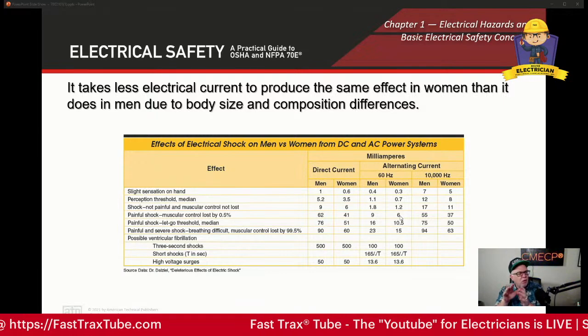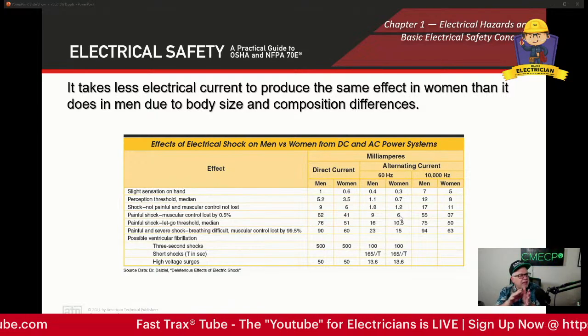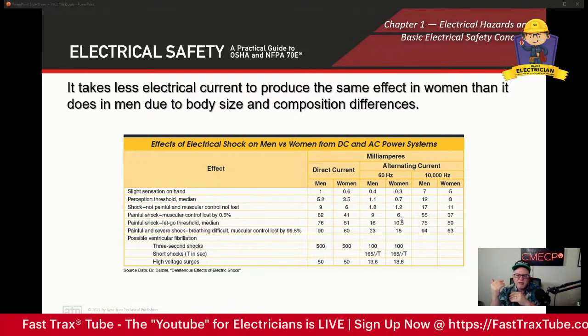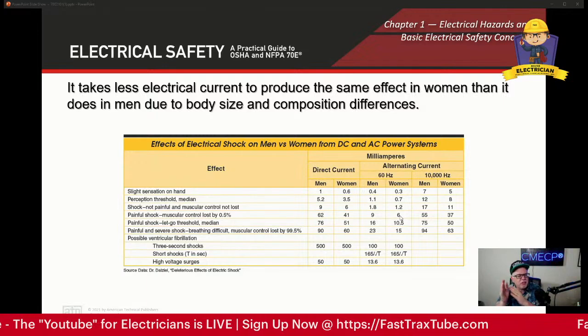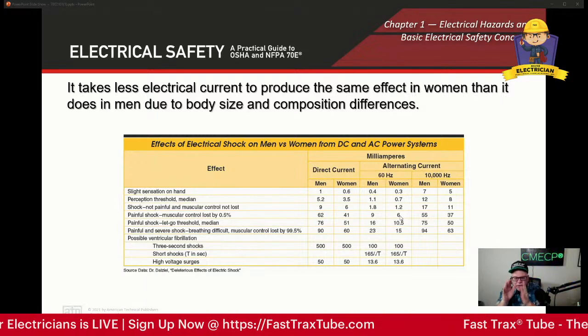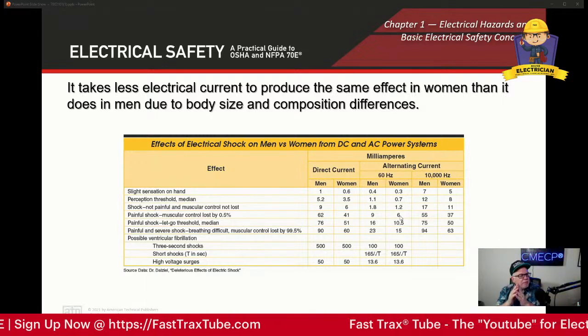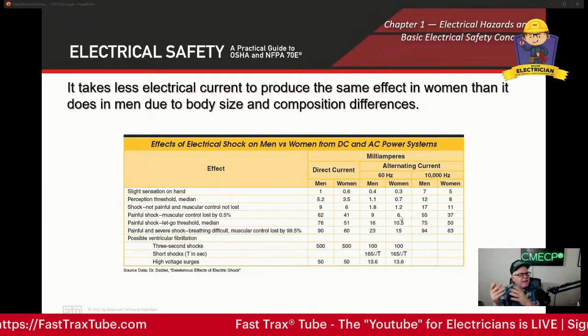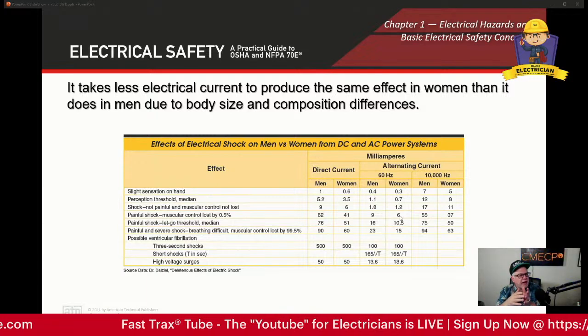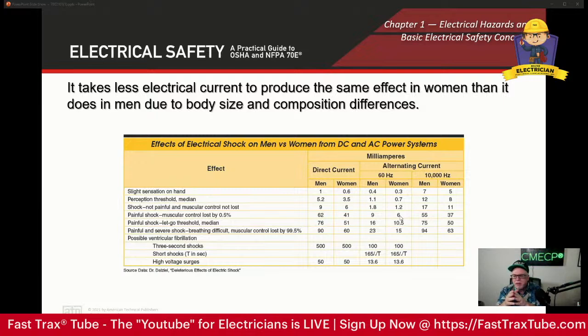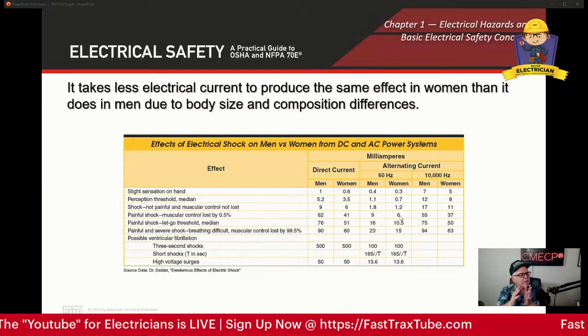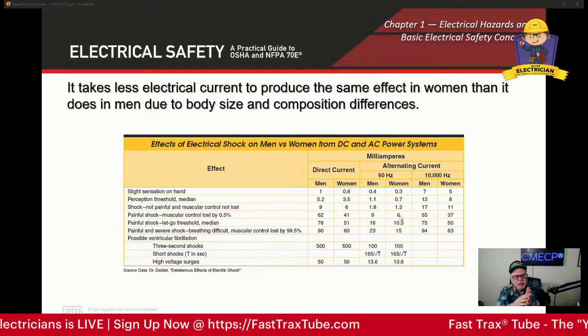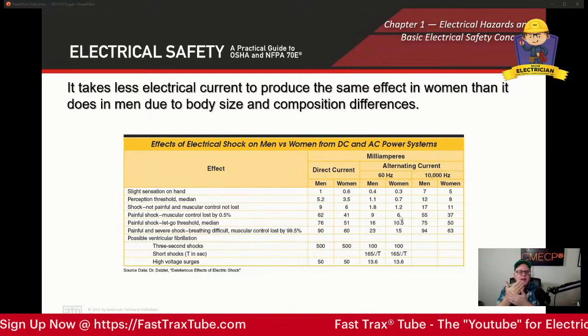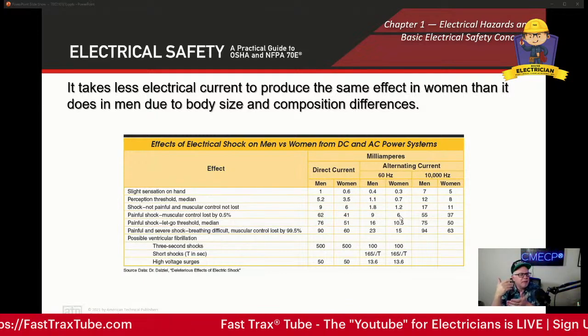Now you might be saying, wait a minute, that's 9 milliamperes. Luckily, a GFCI is going to stop this, because that's at nominal 5 milliamperes. But in a circuit that's not GFCI protected, even at 9 milliamperes for a man or 6 milliamperes for a woman, that muscle control loss could result in a shock reaction.